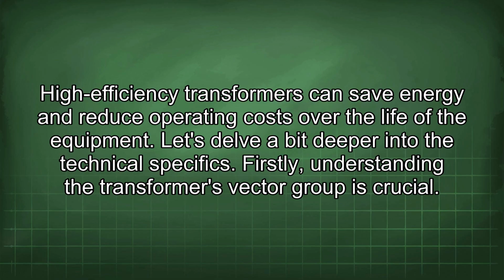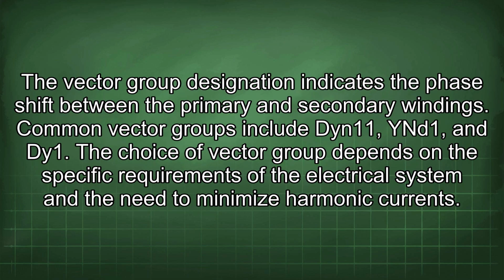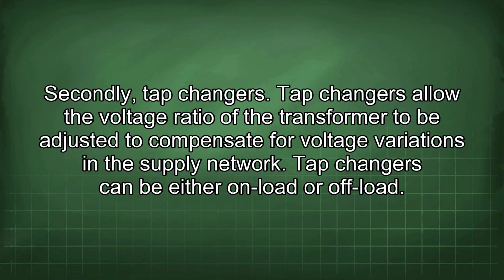Firstly, understanding the transformer's vector group is crucial. The vector group designation indicates the phase shift between the primary and secondary windings. Common vector groups include Dyn11, YNd1, and Dy1. The choice of vector group depends on the specific requirements of the electrical system and the need to minimize harmonic currents. Secondly, tap changers. Tap changers allow the voltage ratio of the transformer to be adjusted to compensate for voltage variations in the supply network.